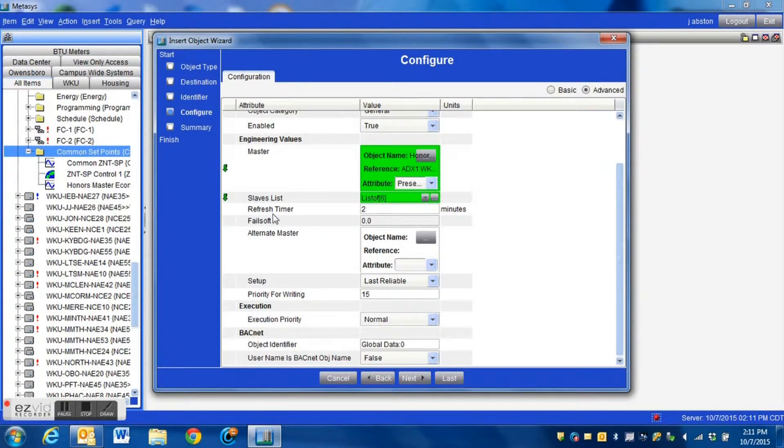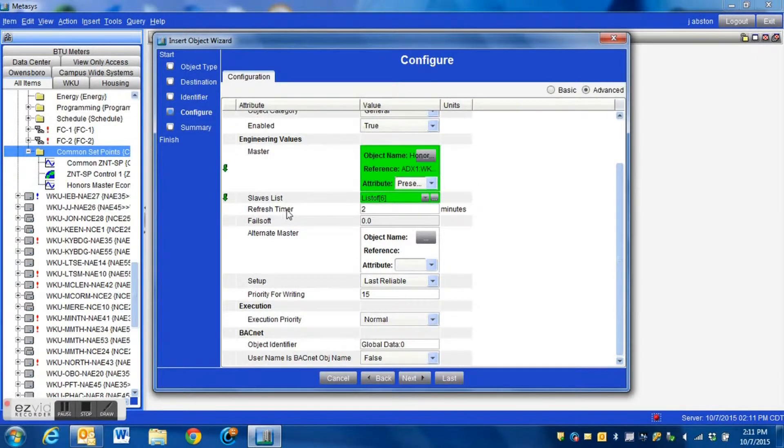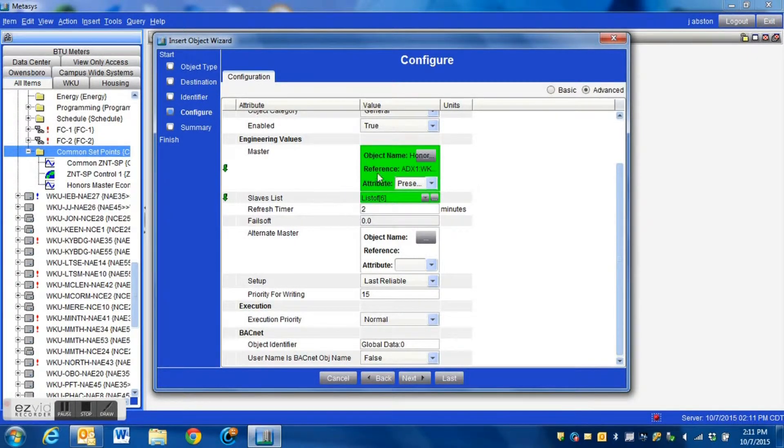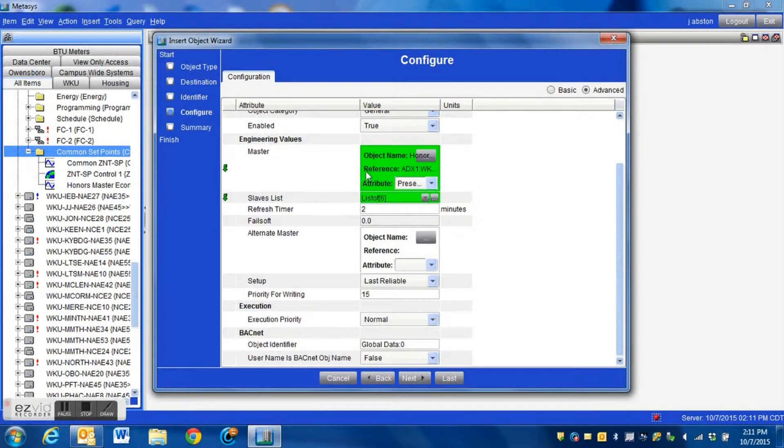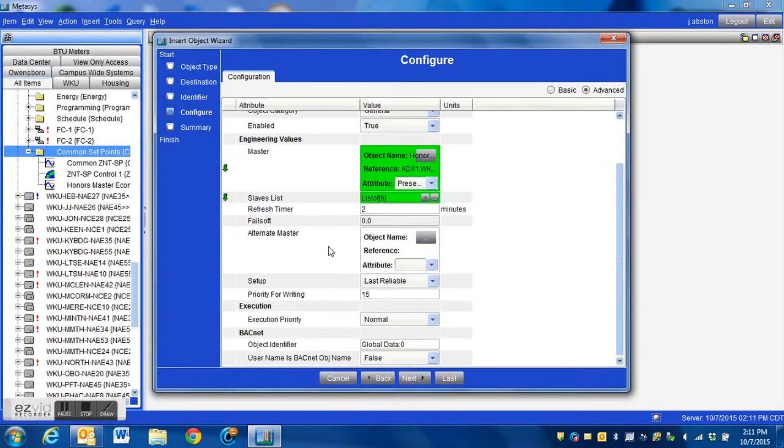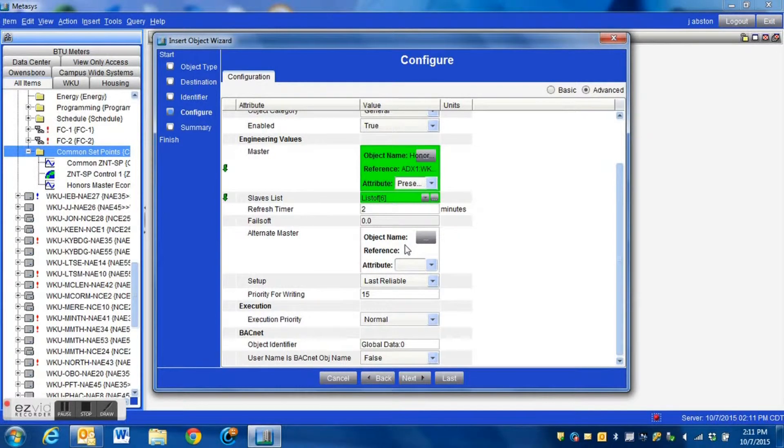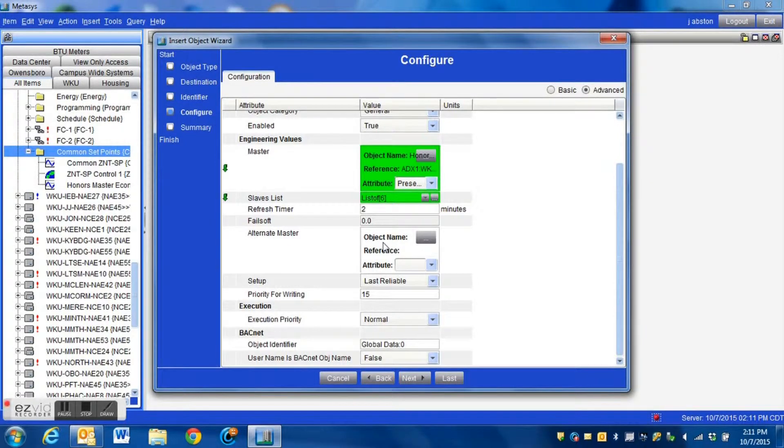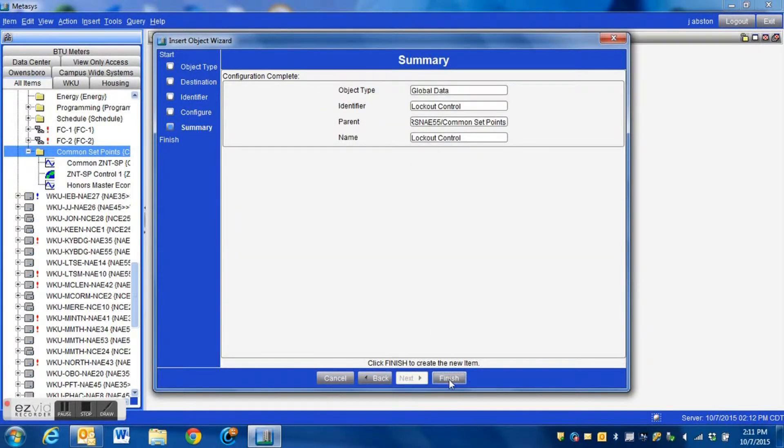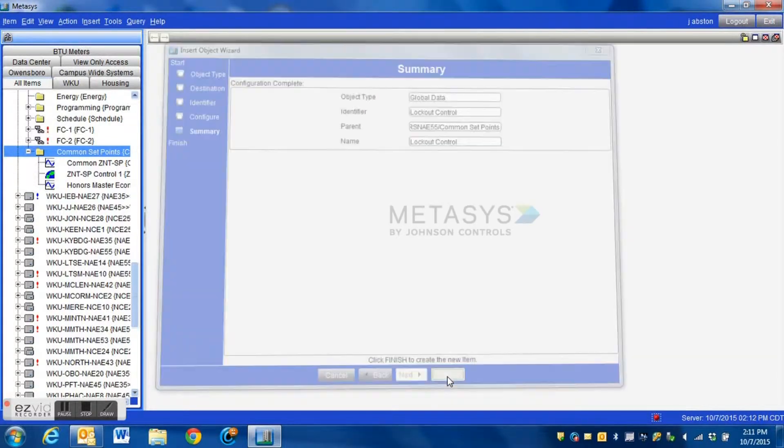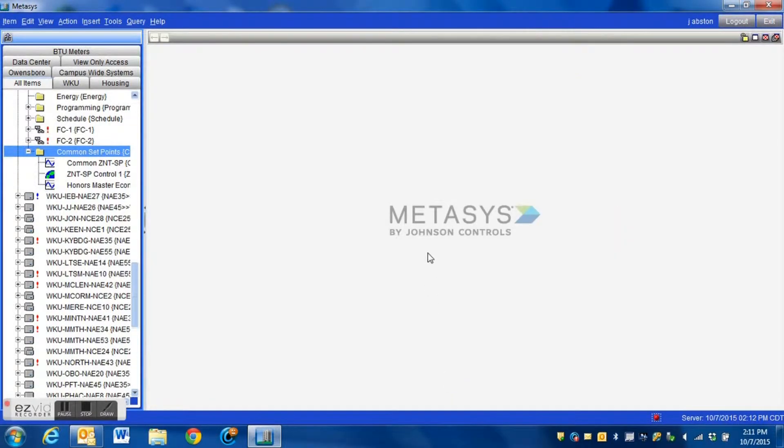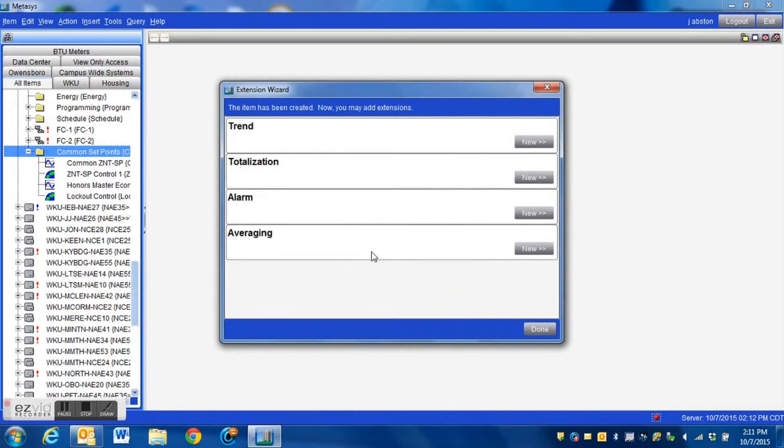I'm just going to hit OK here, we have this pretty much created. This interval time, it's how often that it will recommand and reinitiate that value into each of those lists. It defaults for two minutes, that's a good round value. You can change that to whatever time frame that you need. If you have a system where you need an alternative set point you can add that there, but we're just going to hit next, we're going to hit finish and here we are.